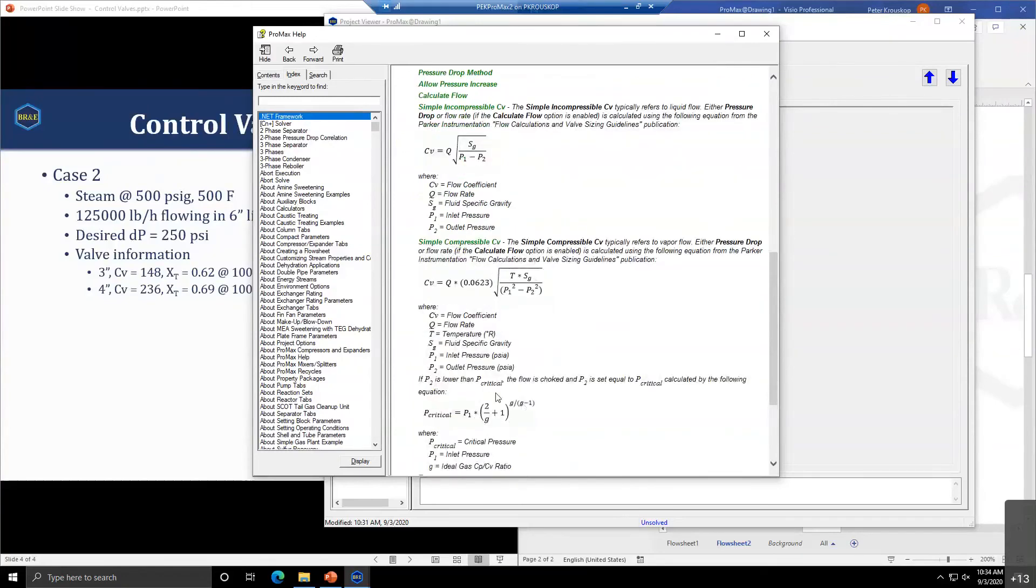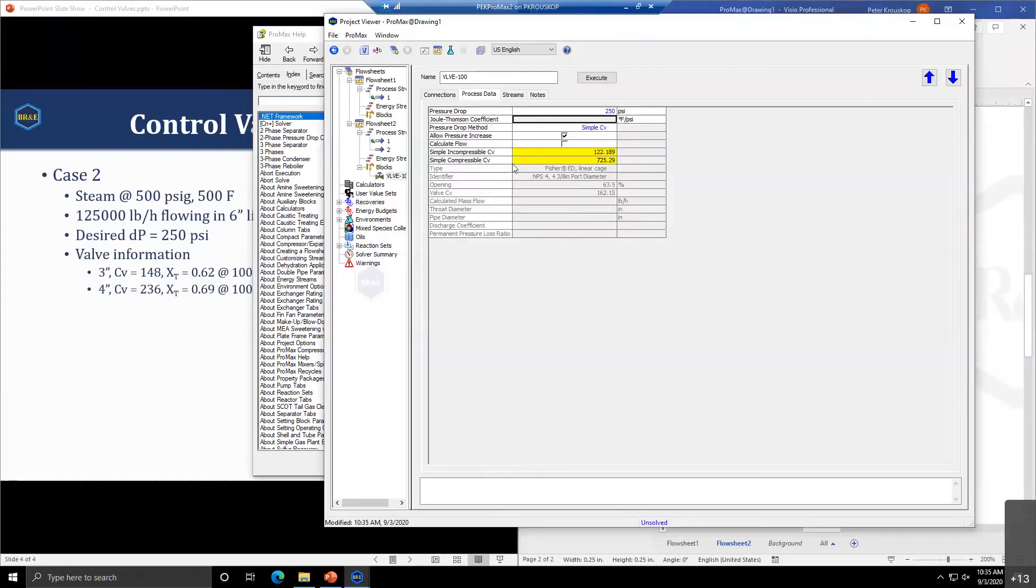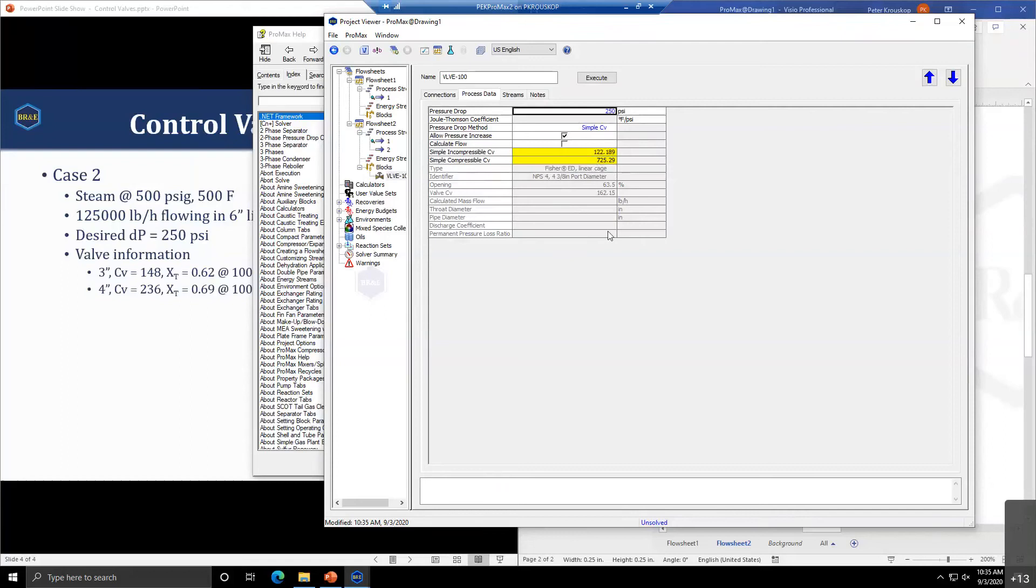The compressible valve does account for critical pressure and it gets calculated. The equation accounts for the temperature of the vapor or compressible fluid, as well as the specific gravity and its flow rate and CV to get the pressure drop. These simple CVs are very simple approximations to what you would expect or need.